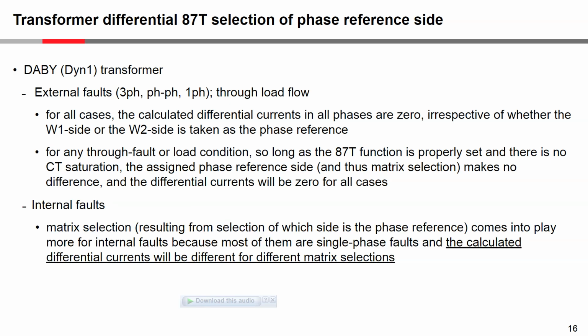However, the issue comes in for internal faults. Matrix selection, resulting from selection of which is the phase reference, comes into play more for internal faults, because most of them are single phase, as with most faults on the network, and the calculated differential currents will be different for different matrix selections. So let's have a look at that.